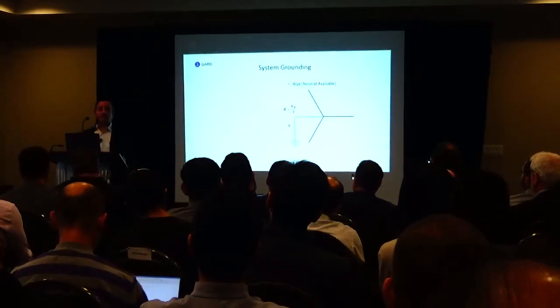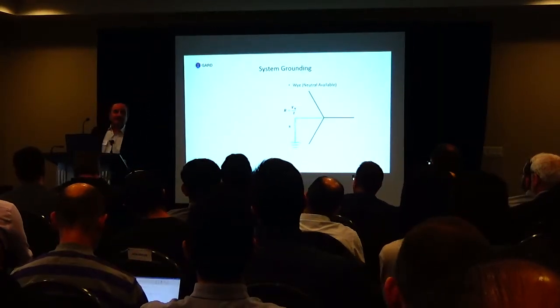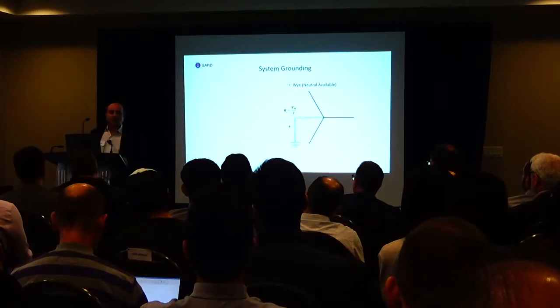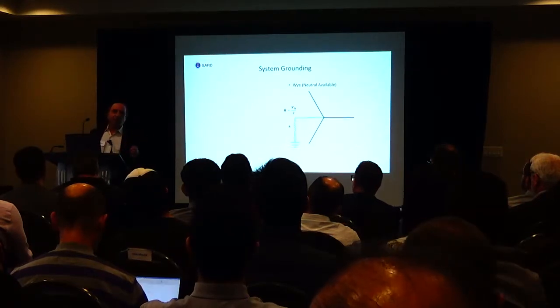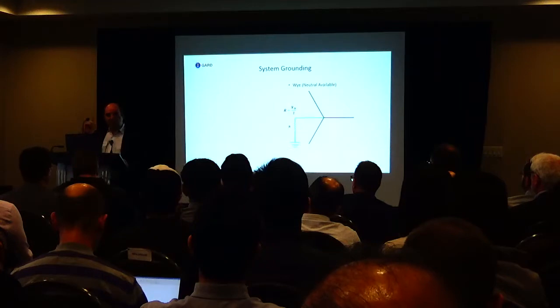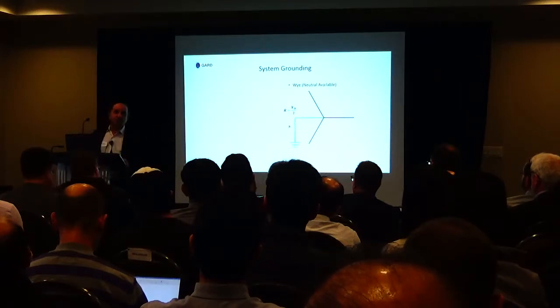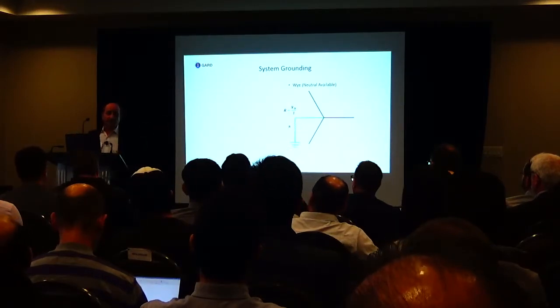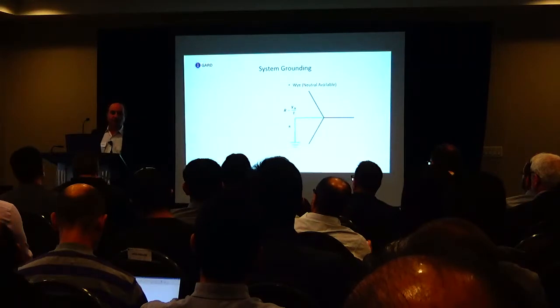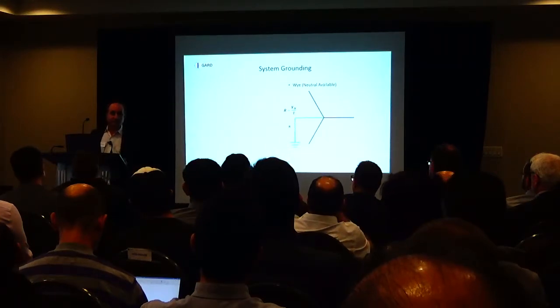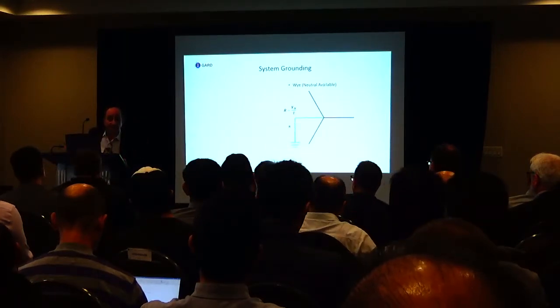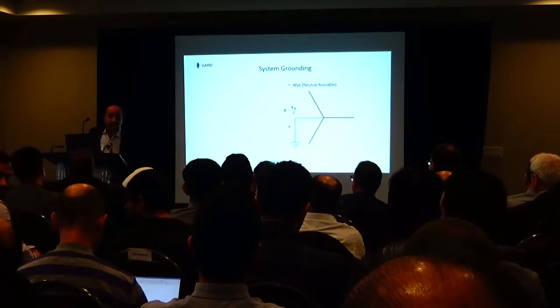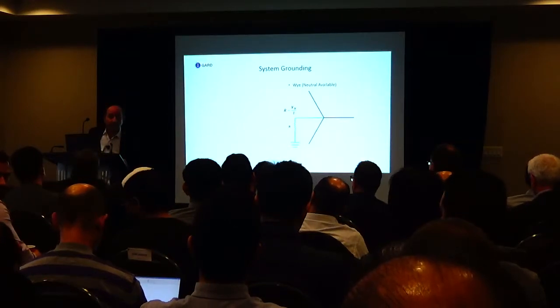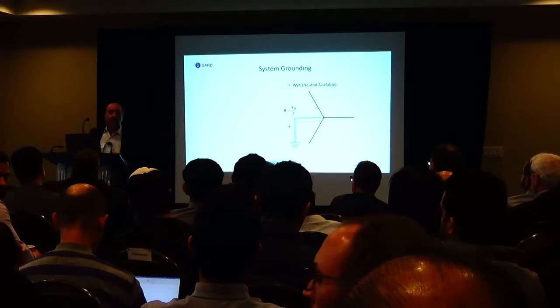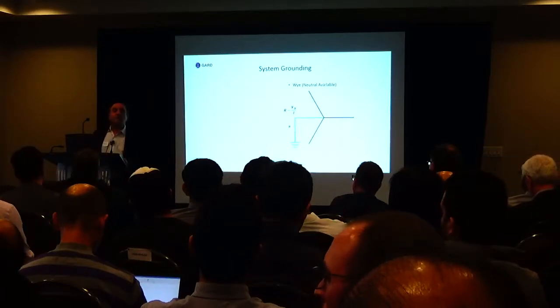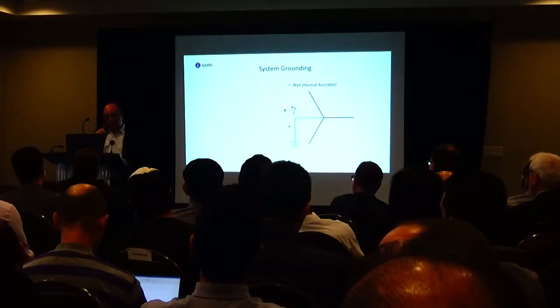On a high resistance grounded system, they say that you have to have qualified people to determine how long the fault is on the system. So now you have to think, okay, I have a fault in that motor. How long can you leave the fault on the system? What I'm getting to is that the probability of arc flash increases because if you leave it long enough, you have a phase-to-phase short circuit sometime. I agree with you.